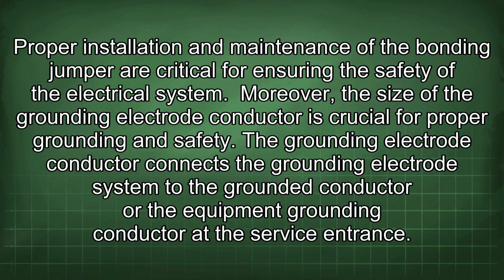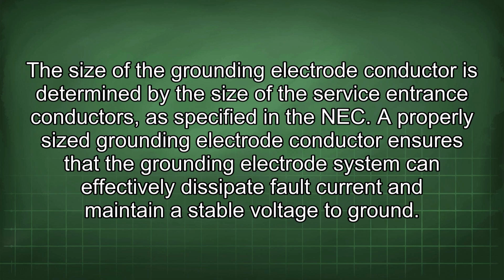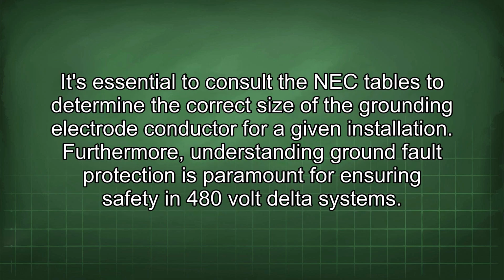Moreover, the size of the grounding electrode conductor is crucial for proper grounding and safety. The grounding electrode conductor connects the grounding electrode system to the grounded conductor or the equipment grounding conductor at the service entrance. The size of the grounding electrode conductor is determined by the size of the service entrance conductors as specified in the NEC. A properly sized grounding electrode conductor ensures that the grounding electrode system can effectively dissipate fault current and maintain a stable voltage to ground.